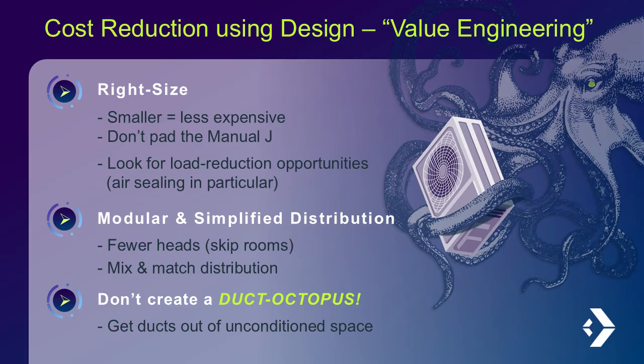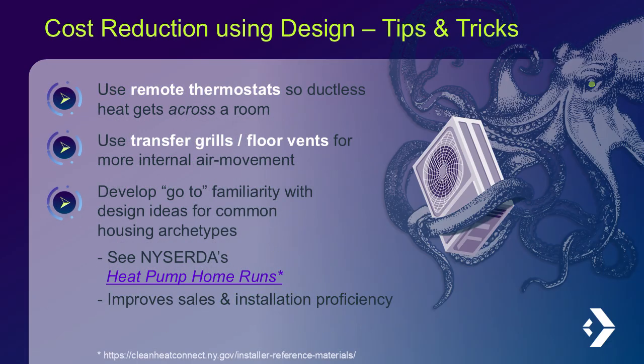Mixing and matching distribution methods like compact ducts and ductless heads can also streamline design, while avoiding overly complex duct systems ensures better efficiency. Moving ducts out of the unconditioned space is also another way to lower the load and boost performance. To improve air movement, consider using remote thermostats, transfer grills, or floor vents. Familiarity with common design strategies for typical housing archetypes can further be explored in NYSERDA's heat pump home runs, available at cleanheatconnect.ny.gov. By applying these strategies, HVAC professionals can deliver cost-effective, efficient, and customized solutions tailored to each home.